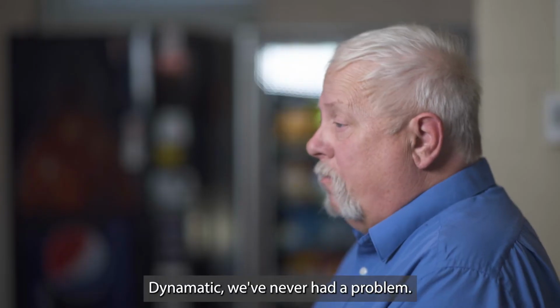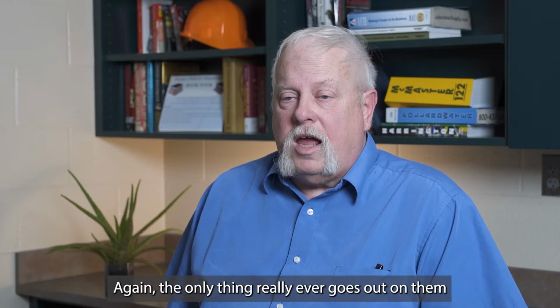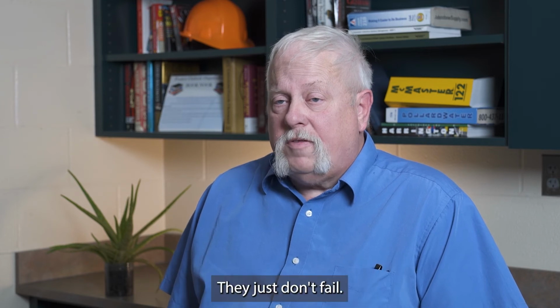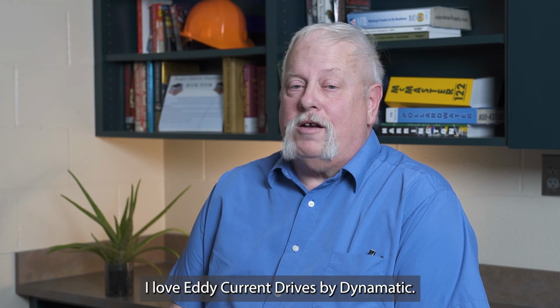Dynamatic, we've never had a problem. They always have repaired our drives quickly. Again, the only thing that really ever goes out on them is either the controller board or the commutator ring and brushes. They just don't fail. I love eddy current drives by Dynamatic.